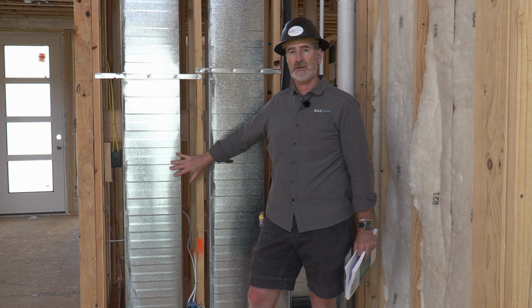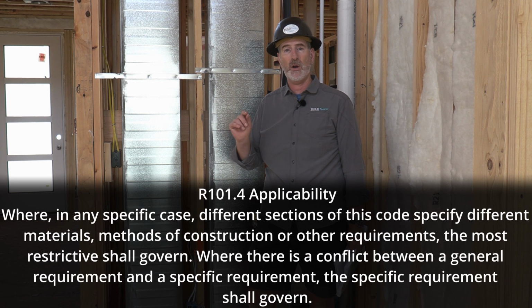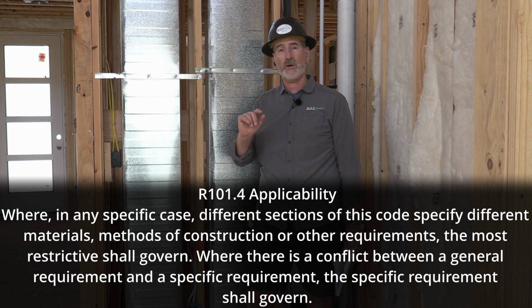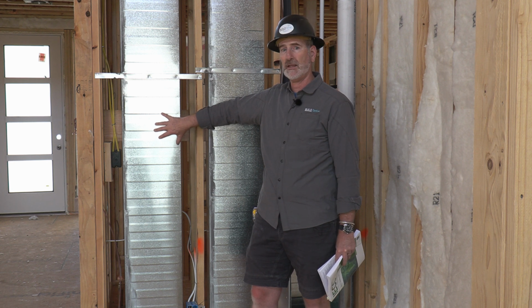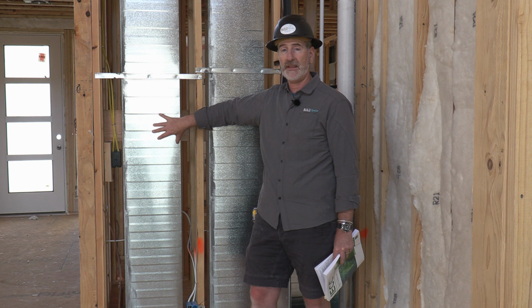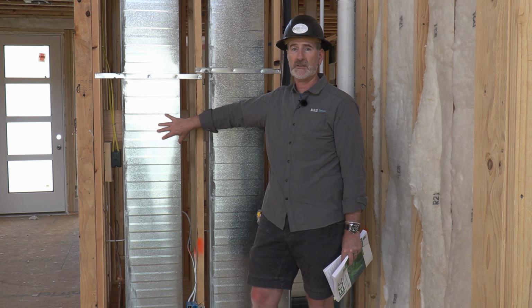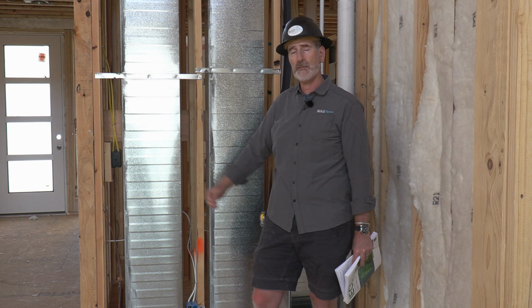And the last thing I wanted to point out, that there's an inconsistency in the code. The energy code says that you can't use the building cavity as a pressurized duct system, but the IRC, the mechanical section of the codes, doesn't necessarily say the same thing. So there is a section in this code as well as in the IRC that's about applicability, which means that the most stringent version of the code, or the best performing compliance section of the code, should prevail. And in this case, having true ductwork inside this cavity is the thing that's going to create the best performance for the house. And so this is the one that should overrule the IRC section that says that you could build a plenum or a cavity that has pressurized air moving through it.